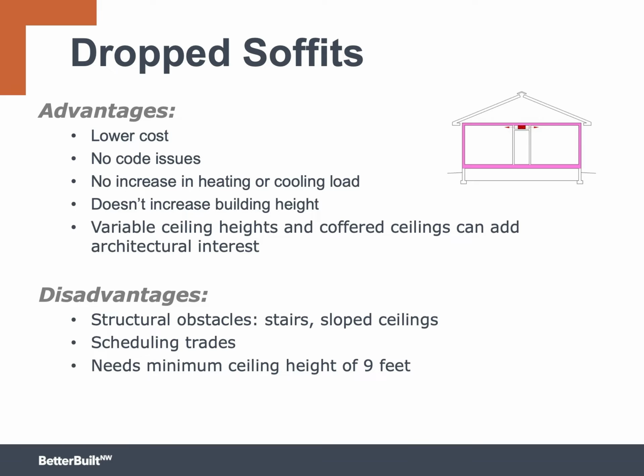One of the simplest methods for ducts inside is the drop soffit. This is ideal for single-story buildings with a central hallway. It's a very popular approach with affordable housing developers who specialize in small single-story homes. Dropped soffits are not expensive, present few code issues, and they don't increase the volume of the conditioned space. In order to maintain an air leakage barrier, the top of the soffit must be enclosed with a rigid material such as drywall or OSB.